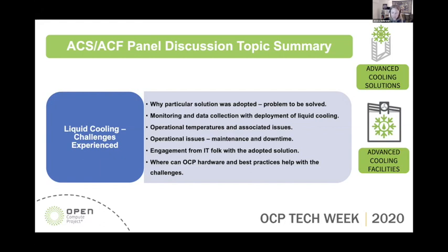For cold plate solutions, you really need to do an analysis of what it is that you want, because you might be able to take heat out of the CPU and the DIMMs to reduce fan speeds a lot. So operational costs will go down with liquid cooling, but you also need to look at the hardware costs needed to procure the cold plate liquid cooling solution, as well as the DIMM liquid cooling solutions. So it's about doing that analysis of how much heat you'd like to capture within the liquid versus the air.